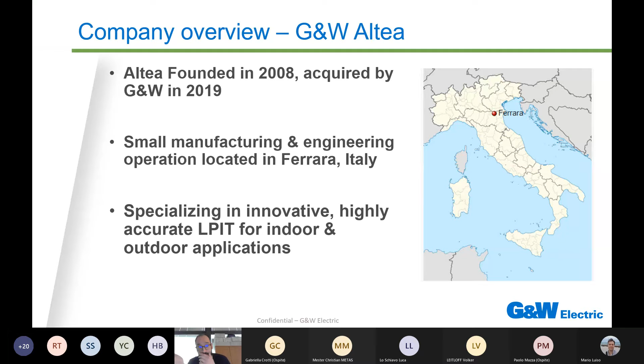So our product portfolio can go from standalone low-power instrument transformers to embedded low-power instrument transformers, where we embed voltage and current sensing in already existing medium voltage equipment. Our technology is for the voltage sensor capacitive divider and for the current sensor Rogowski coil.